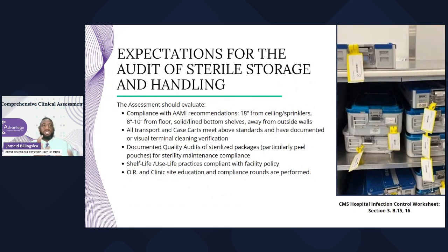All right, let's go to the sterile storage, right? Sterile storage, make sure we're compliant with AAMI recommendations: 18 inches from ceilings or sprinklers, 8 to 10 inches from the floor, solid bottom shelves, away from outside walls. All transport and case carts meet the above standard. So a lot of times we go into places and they have the solid bottom and all that stuff. And then I'm seeing a cart and we just use this to take trays to the OR. But that cart doesn't have a solid bottom.